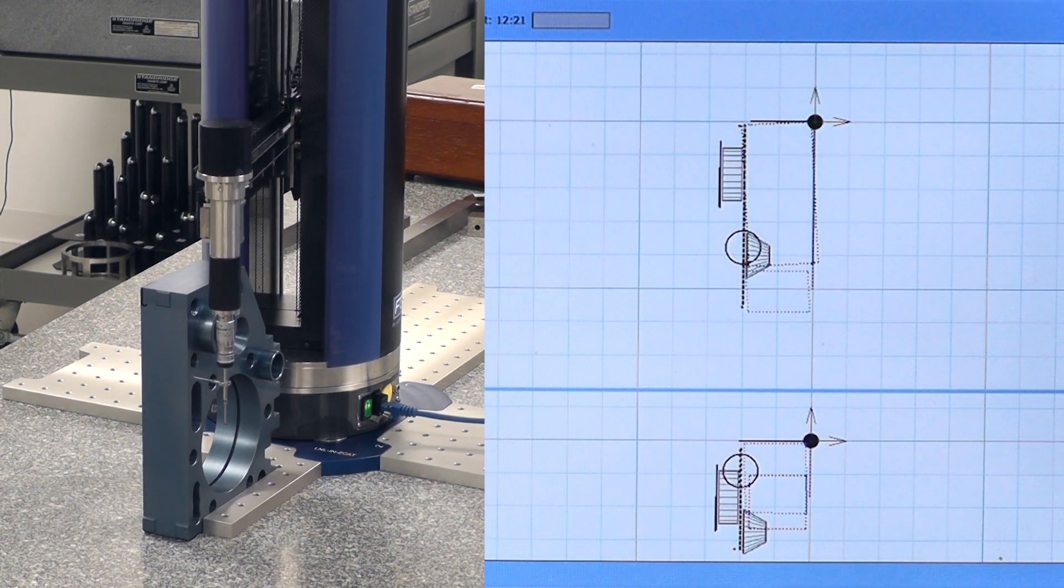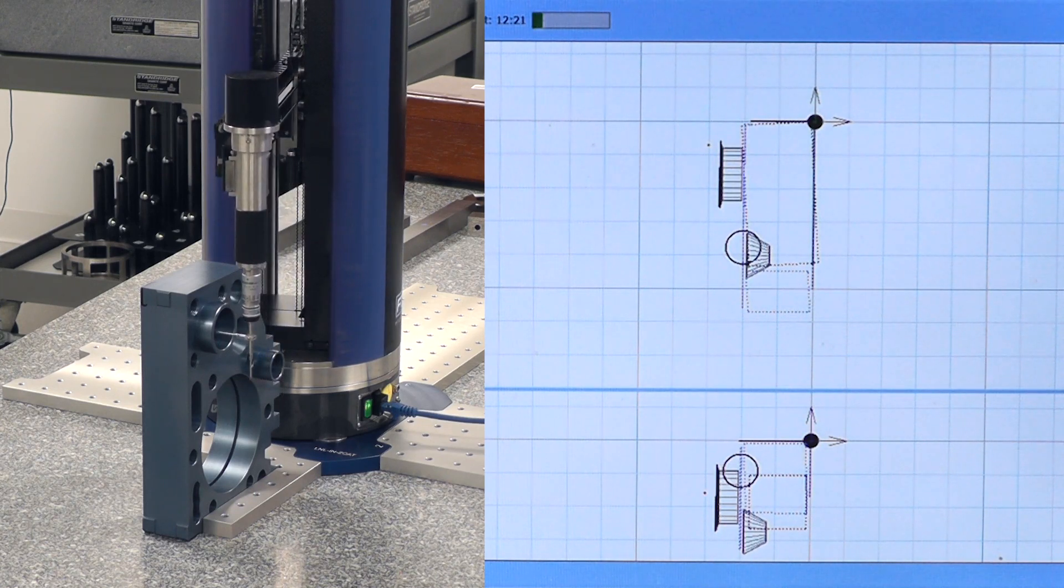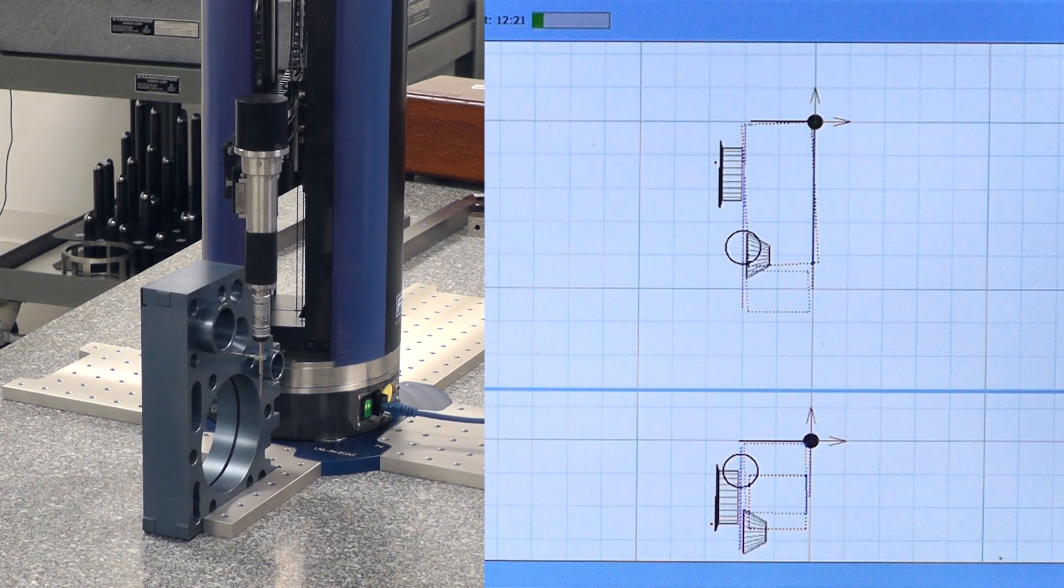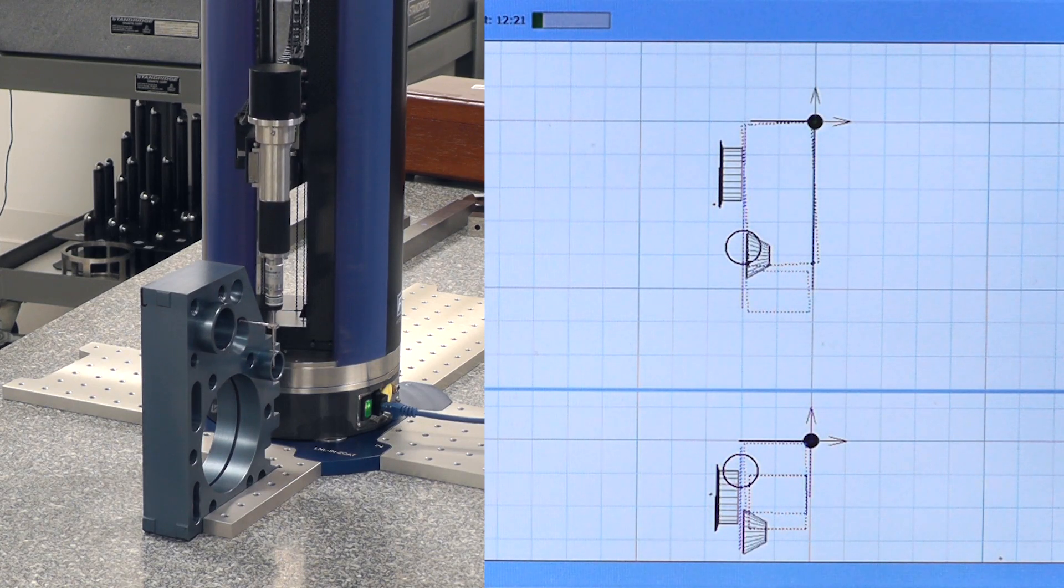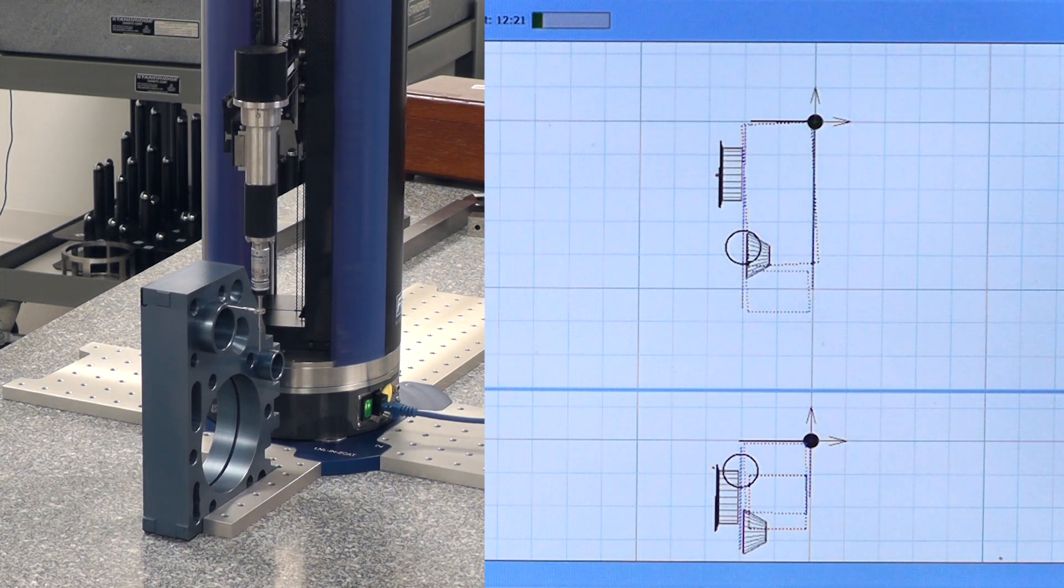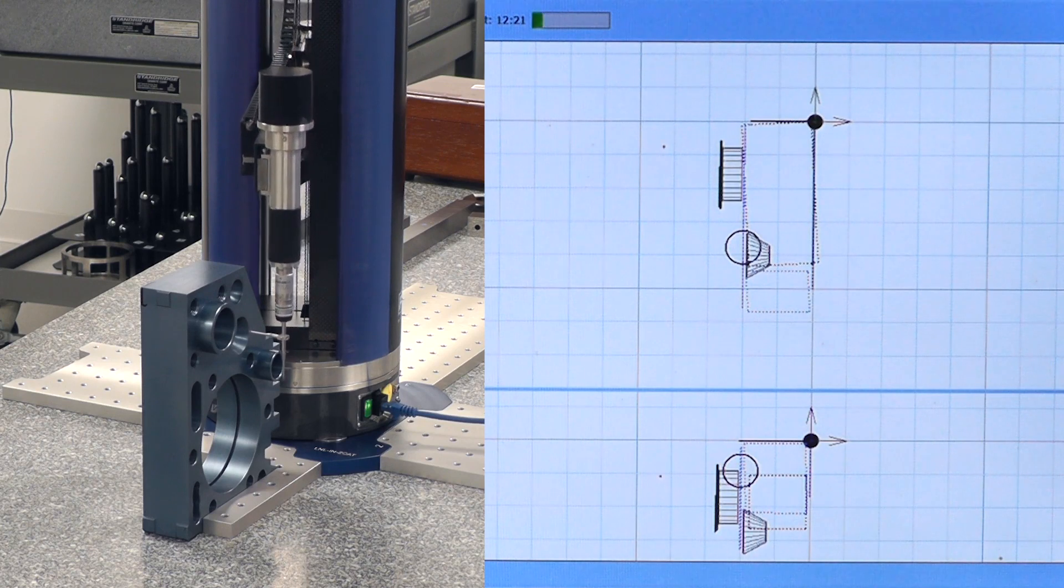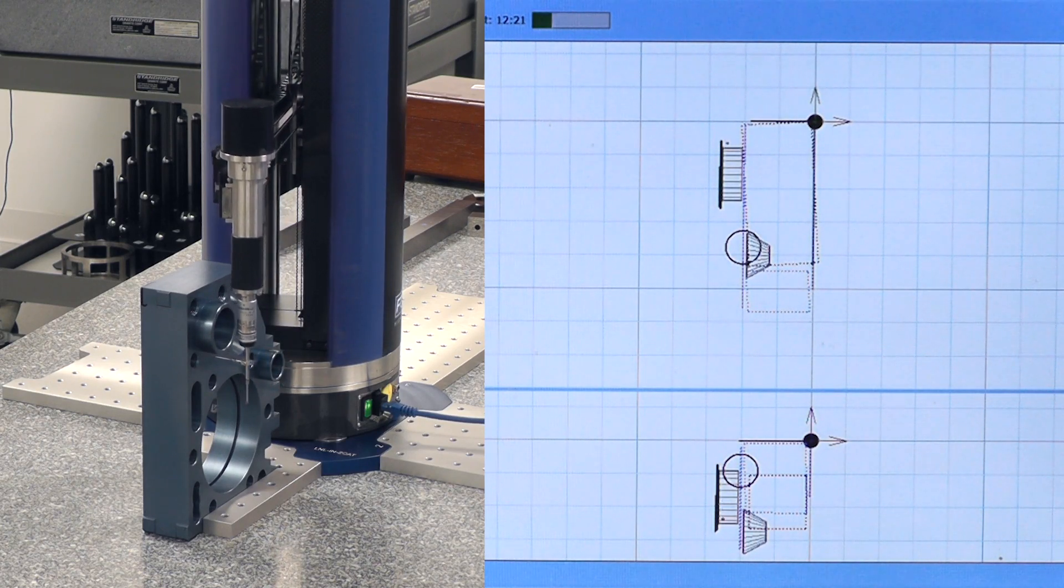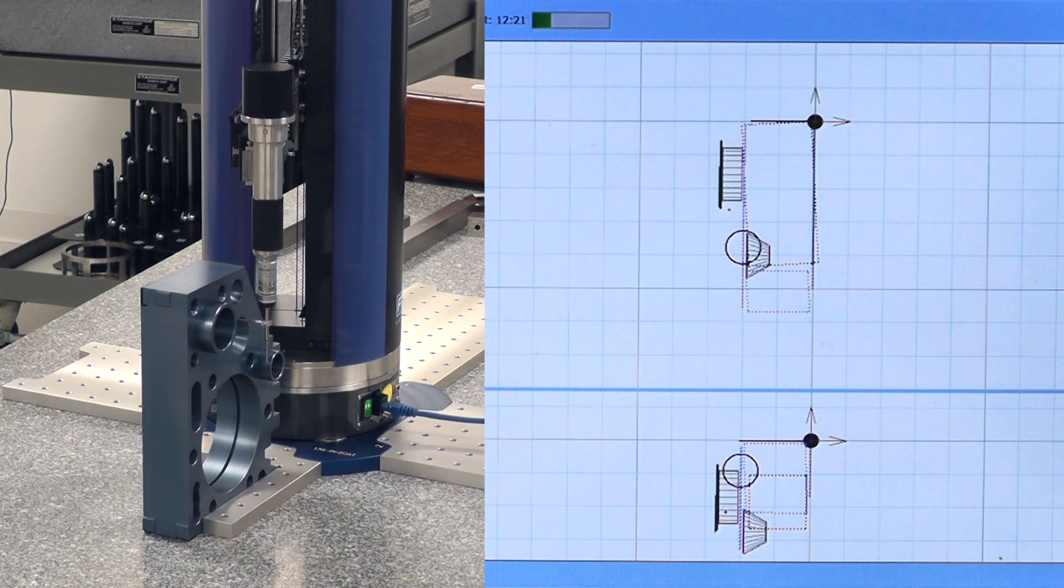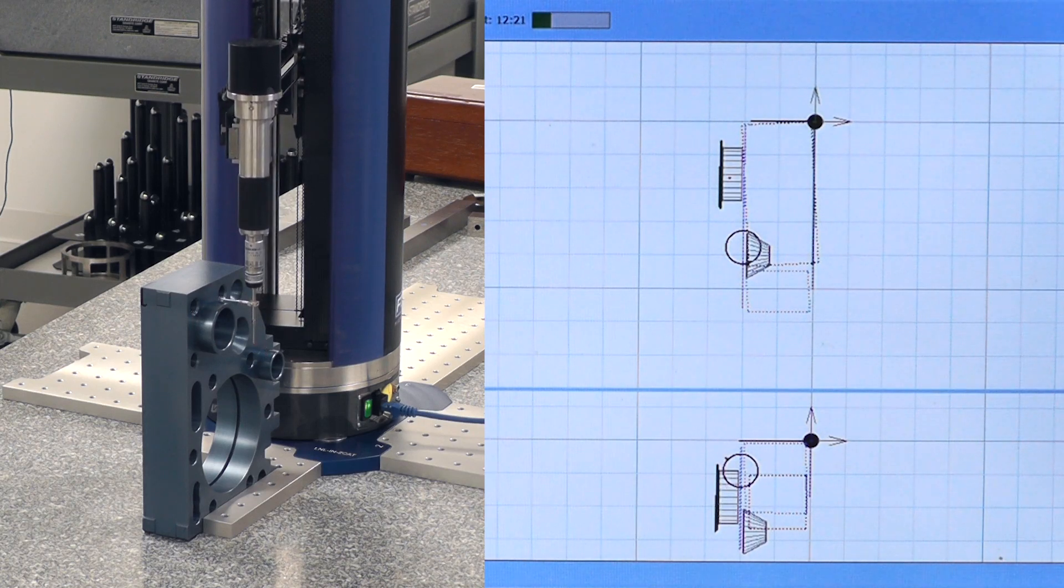Now it's measuring a plane. Because when we're using the ZCAT or any other CMM, when you start measuring diameters and cones and lines, it likes to reference off of a plane. So the first thing I do a lot of times is measure a plane so I can reference off that. Here I actually measured another plane on the top of that cylinder. And now I told it to measure the outside diameter of that cylinder. And we're using strictly the horizontal probe. So we're doing a lot of the same things we did before.